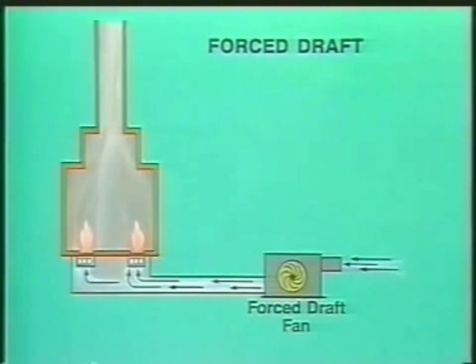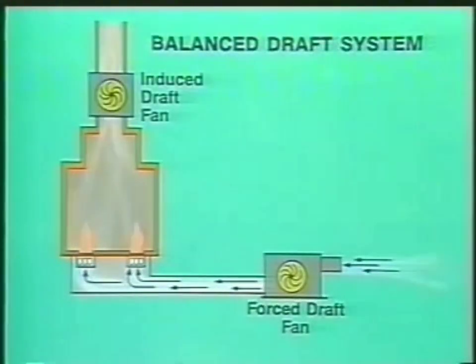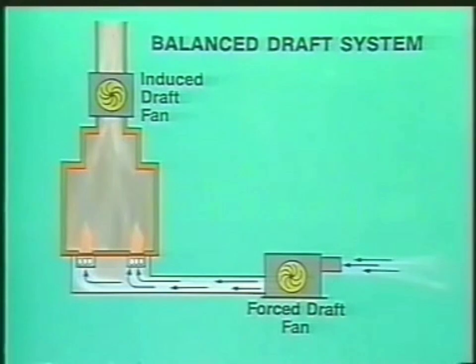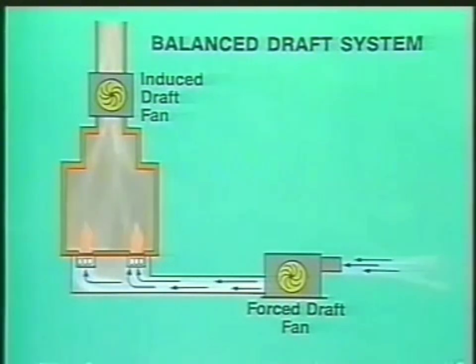Fired heaters which use both forced and induced draft fans are called balanced draft furnaces. In this system, a forced draft fan supplies air for combustion while the induced draft fan pulls the flue gases from the firebox to maintain a negative pressure in the furnace.